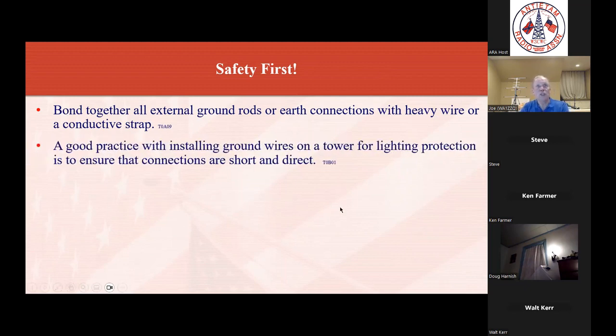A good practice with installing ground wires on a tower for lightning protection is to ensure that connections are short and direct. You want to go straight to that ground and make that connection as short as possible. And when you're talking lightning protection, you want to avoid bends in the wire, like right angle bends, if you can at all avoid it.